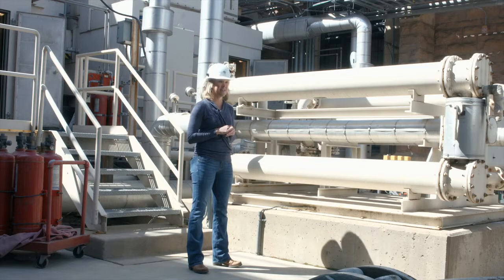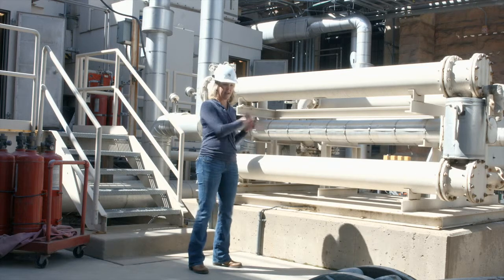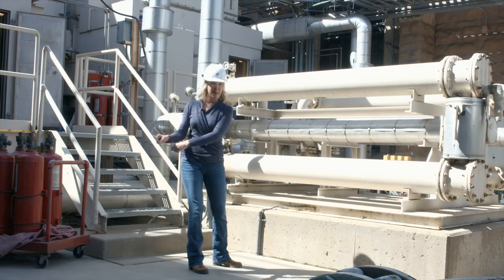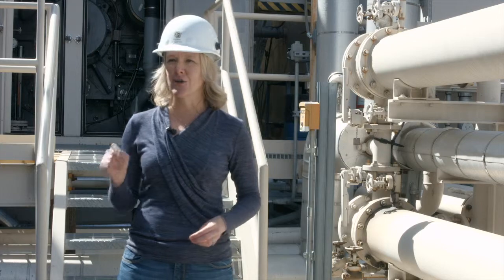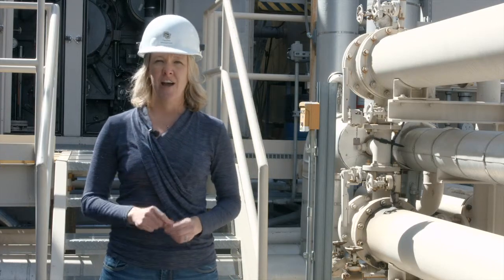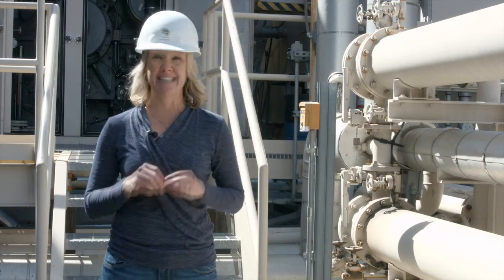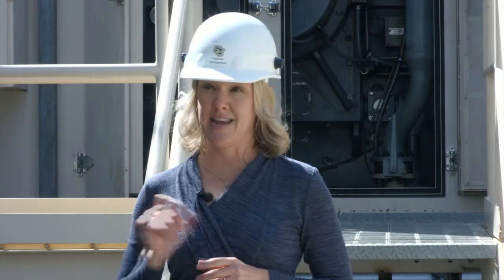The other thing to consider is that at a once-through plant, the water that comes into the plant, when it's spit back out into that reservoir, stream, or lake, is on average 17 degrees Fahrenheit warmer. There are power plants where the effluent temperatures exceed 90 degrees Fahrenheit, and in some cases, 100 degrees Fahrenheit. You might be okay with that if you're a bass, but if you're a trout, you might not be too thrilled about it. So there have been challenges with this around the country, particularly on the East Coast, where we have a lot of once-through plants.